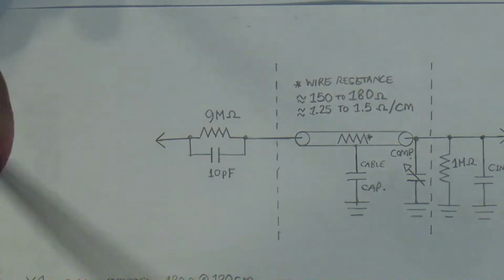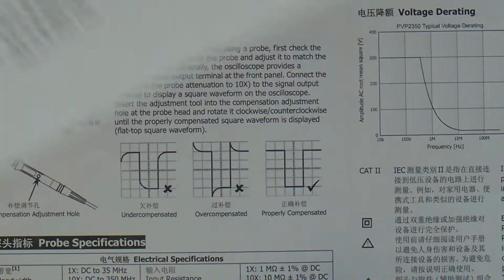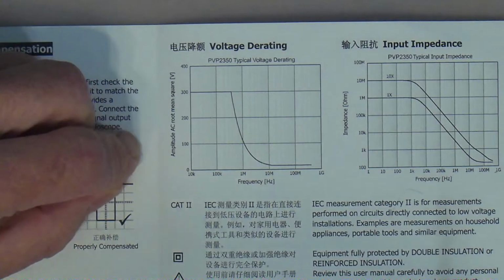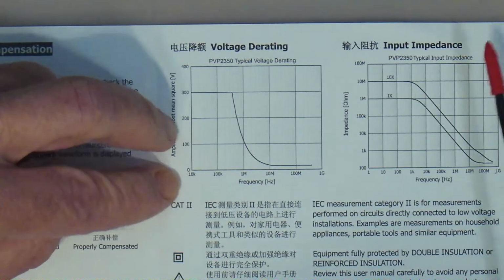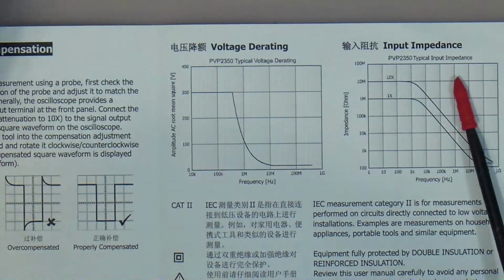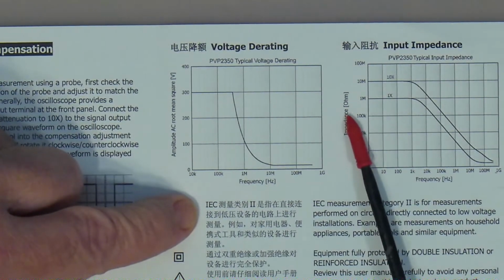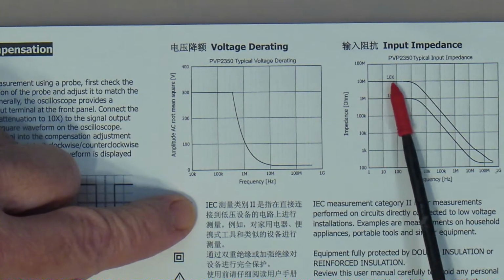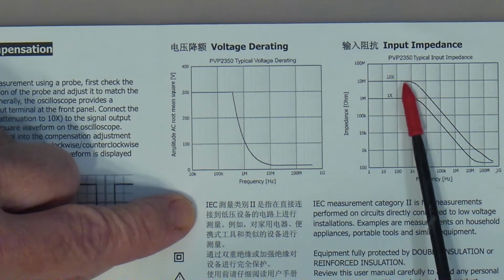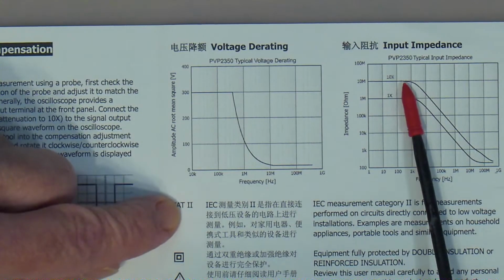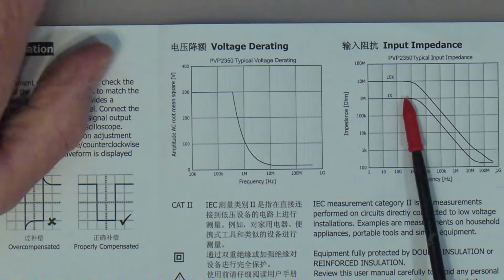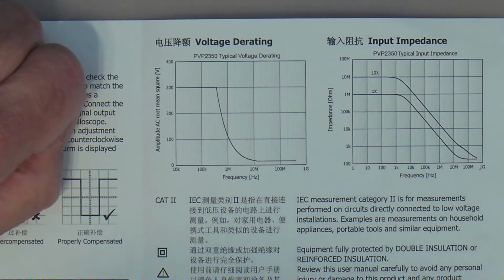Now, the thing to highlight again is this input impedance that we were talking about before. For instance, if you have a 10 times probe, which is what we're dealing with, at 1 hertz the input impedance, as this little graph showed, is going to be 10 megohms. But if you increase the frequency to 1 megahertz, for a common probe, not just this one, on average that value may decrease to 17.4 kiloohms. And at 100 megahertz, it might only be 174 ohms.